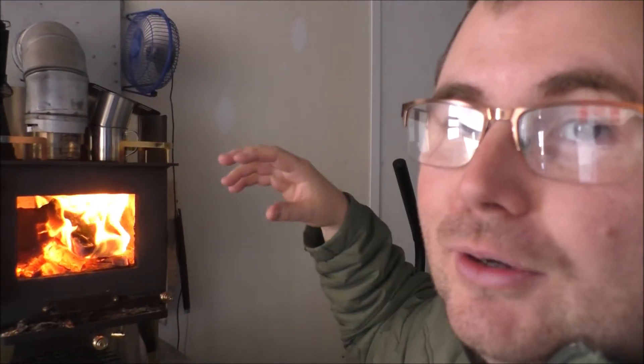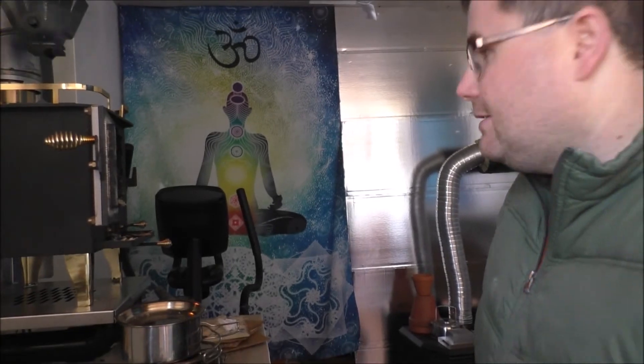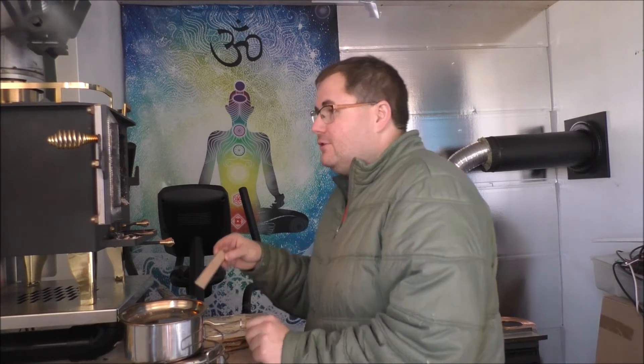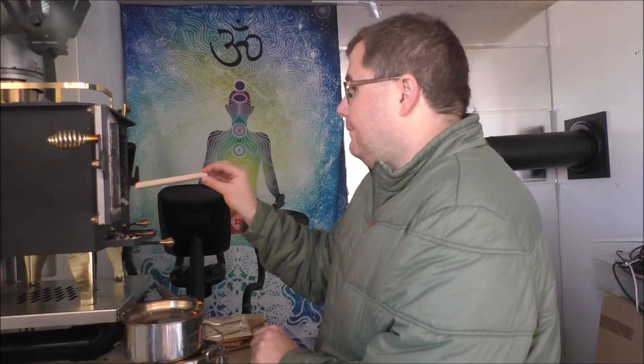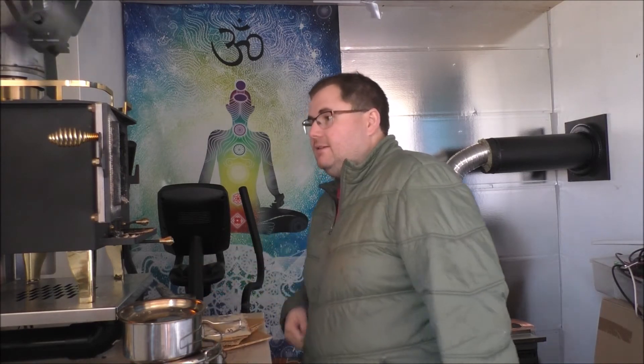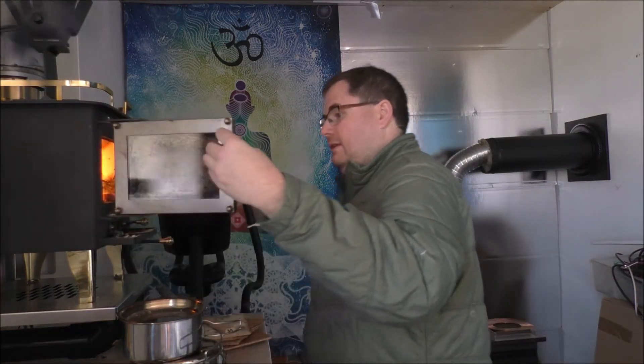So it's very good practice to burn it wide open. See, I got this damper open, got this damper open, and I got the front door open, so it's getting 100% air. Do it for a couple hours, then damp your stove down. That way every time you do it, it clears out your flue. Right, simple. Real simple.